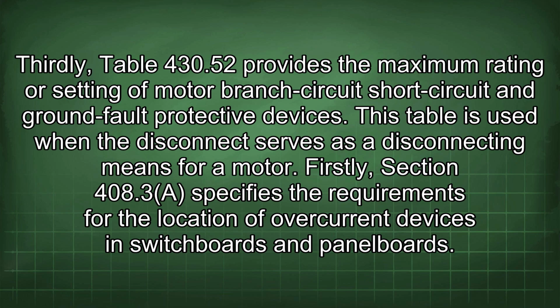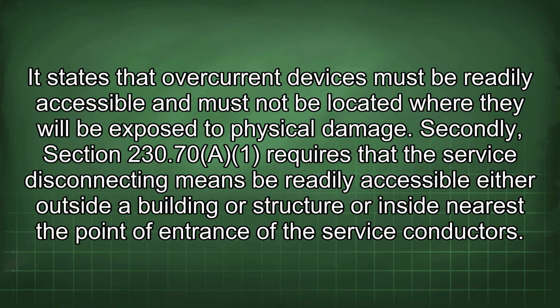Thirdly, Table 430.52 provides the maximum rating or setting of motor branch circuit short circuit and ground fault protective devices. This table is used when the disconnect serves as a disconnecting means for a motor. Firstly, Section 408.3 specifies the requirements for the location of overcurrent devices in switchboards and panel boards. It states that overcurrent devices must be readily accessible and must not be located where they will be exposed to physical damage. Secondly, Section 230.70(A) requires that the service disconnecting means be readily accessible either outside a building or structure or inside nearest the point of entrance of the service conductors.